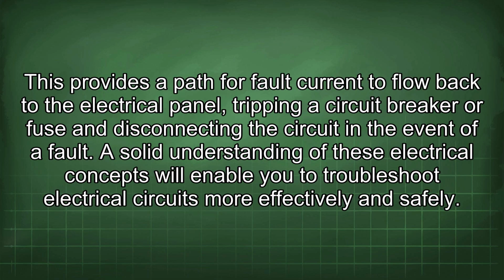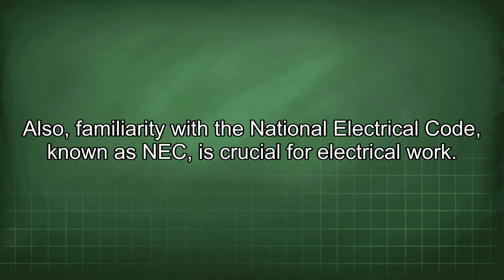Grounding is the process of connecting electrical equipment to the earth. This provides a path for fault current to flow back to the electrical panel, tripping a circuit breaker or fuse and disconnecting the circuit in the event of a fault. A solid understanding of these electrical concepts will enable you to troubleshoot electrical circuits more effectively and safely. Also, familiarity with the National Electrical Code, known as NEC, is crucial for electrical work.